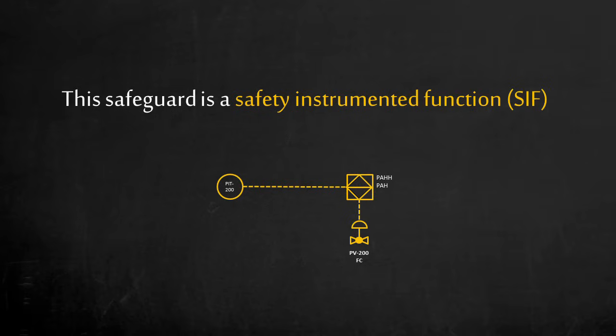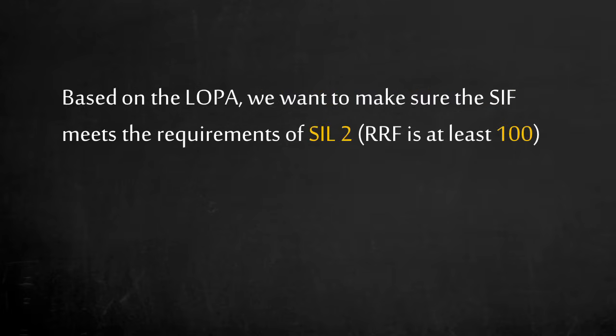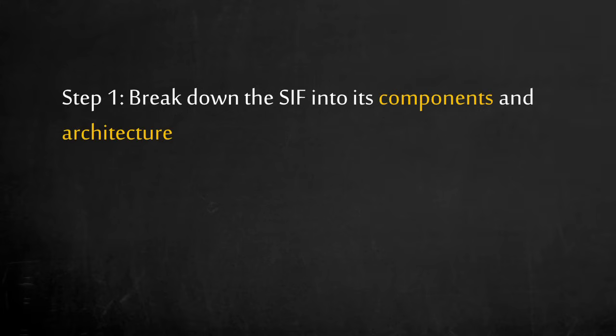The high pressure shutdown is a safety instrumented function, which consists of a sensor, a logic controller, and the final element. Based on the LOPA, we want to make sure the safety instrumented function meets the requirements of SIL2, which reduces the risk by 100 times. Let's break down the SIL study into five steps. Step 1. Break down the safety instrumented function into its components and architecture. Let's take a look.